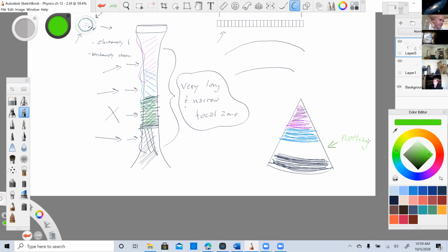So if the innermost ring, the most superficial, if the purple ring were to malfunction, then we would have nothing at the top of the screen. But that's not what happened in our case. Our third from the middle ring malfunctioned. So this ring was good, this ring was good, this ring was bad, and then the final last ring was good.